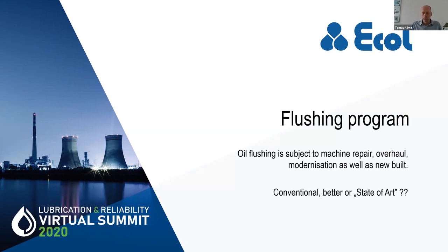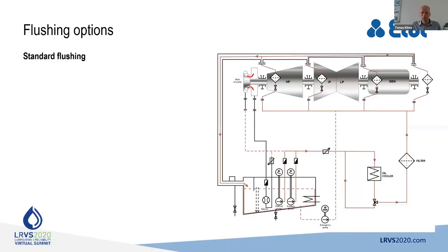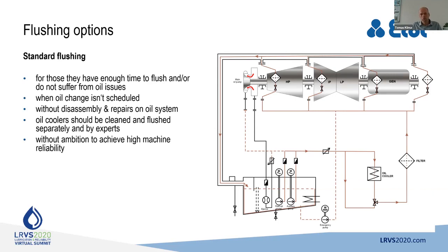You can do conventional, you can do better, you can do state of the art as we used to do over the years. The standard flushing, standard means good, so good for those who have enough time to flush, or who do not suffer with any issue with oil. They do not open the system, doing any disassembly, doing any repairs. They are not exchanging the oil. Then standard flushing is okay, and you can reach the goal. If not, the flushing will take a lot of time, because the flow in pipes is laminar, and you will not reach any effective flushing of the pipes. So this is just like washing the glass with water or cleaning it properly and then having a good drink.